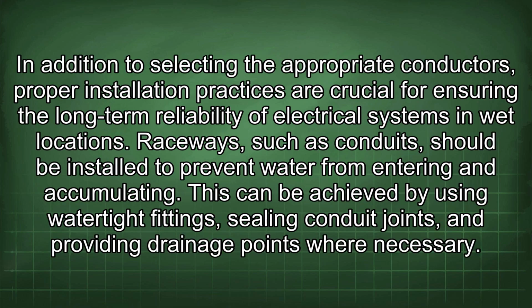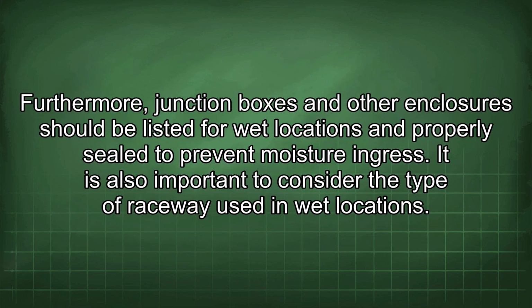In addition to selecting the appropriate conductors, proper installation practices are crucial for ensuring the long-term reliability of electrical systems in wet locations. Raceways, such as conduits, should be installed to prevent water from entering and accumulating. This can be achieved by using watertight fittings, sealing conduit joints, and providing drainage points where necessary. Furthermore, junction boxes and other enclosures should be listed for wet locations and properly sealed to prevent moisture ingress.